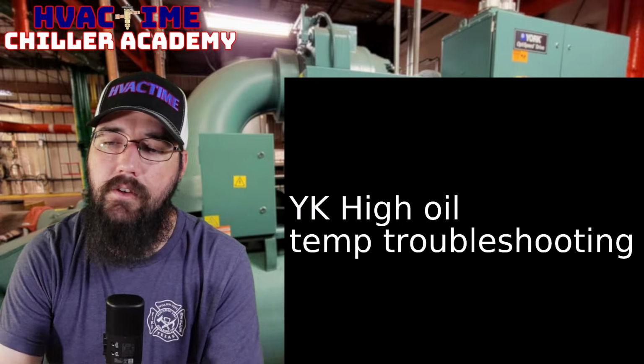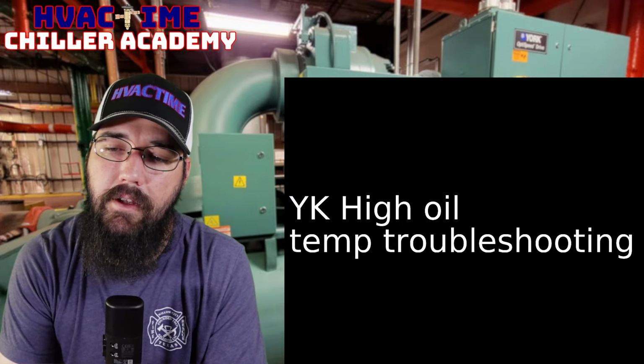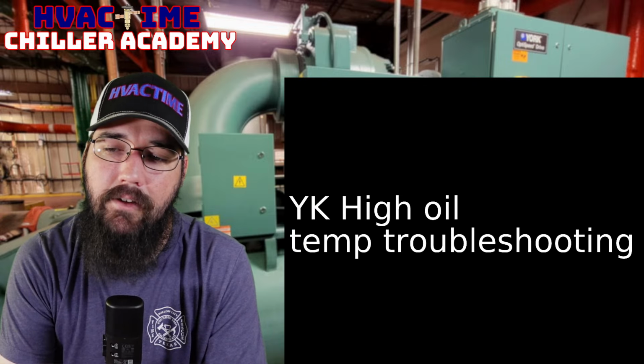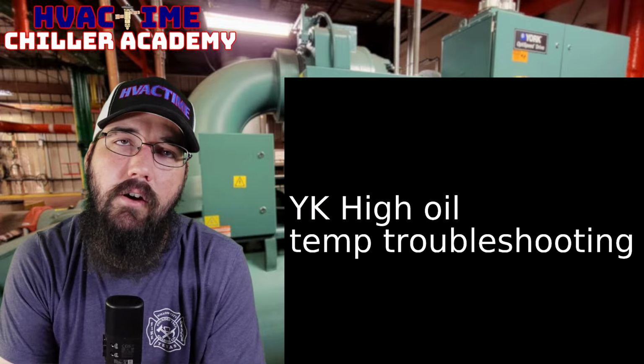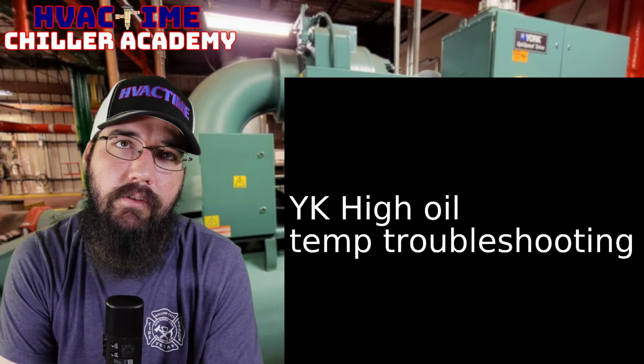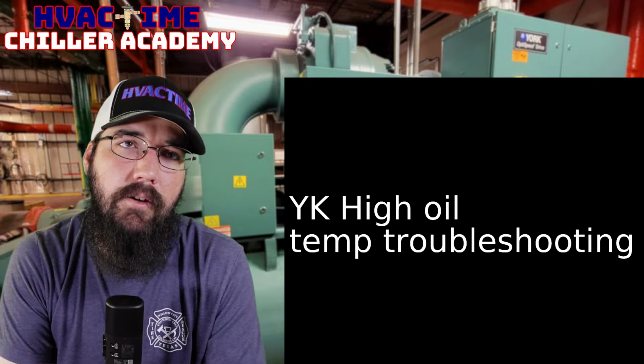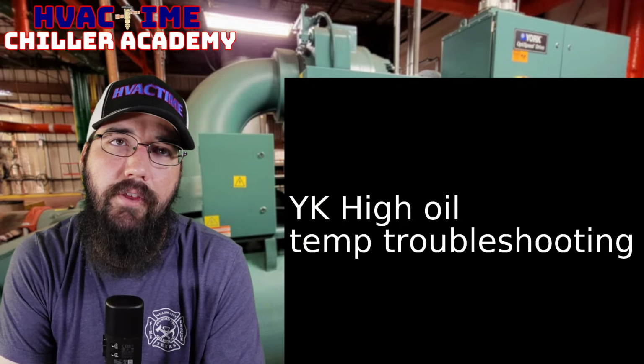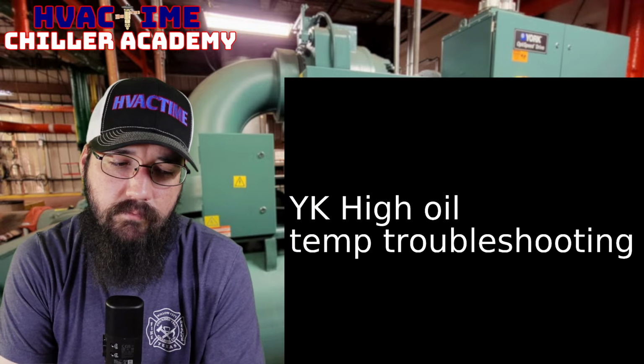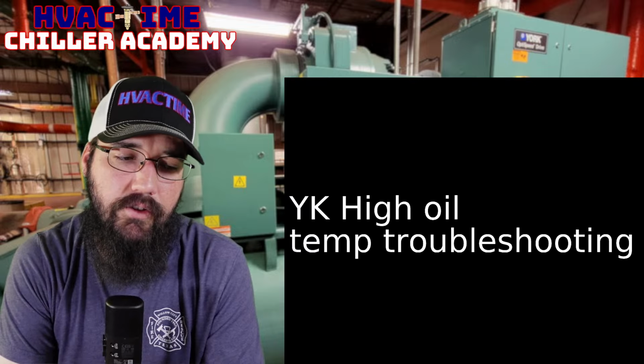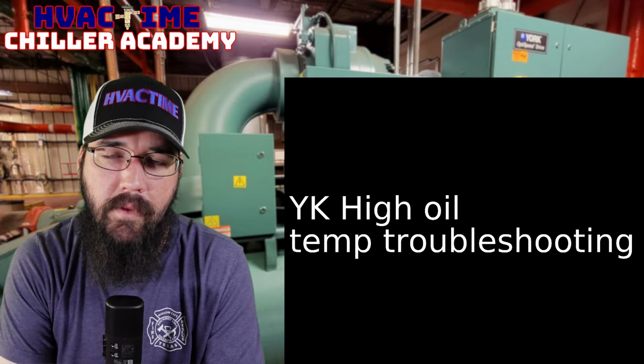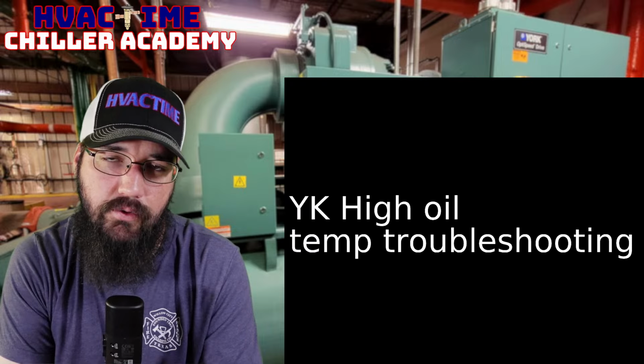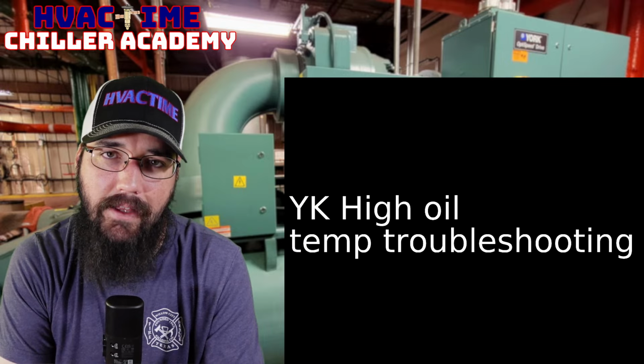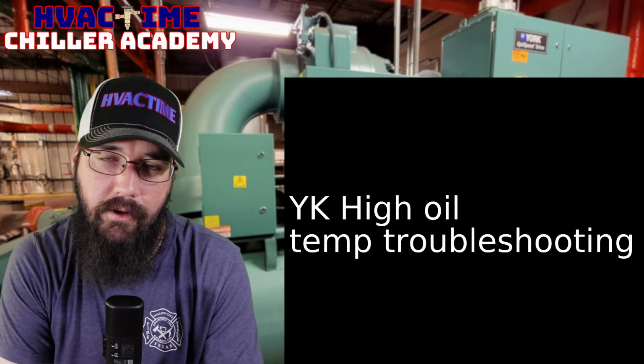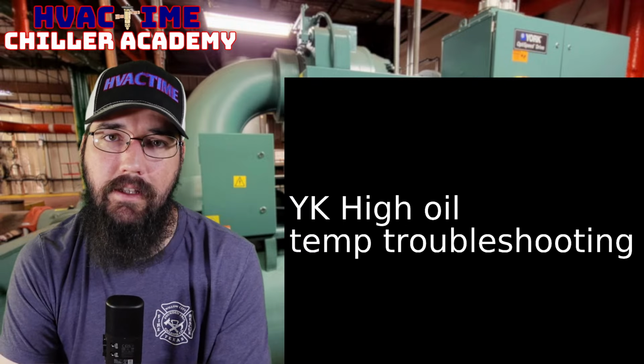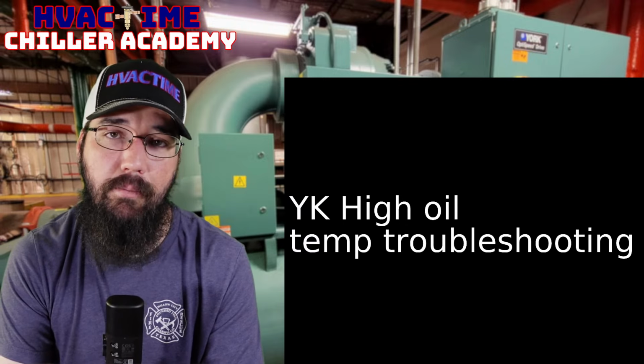So I don't think so. Then the next part of that question would be: does the condenser water increasing in temperature have an impact on the oil temperature? Well, it's going to increase our head pressure. It's going to increase our condenser pressure, obviously. So the only reason I would think that would affect our oil temperature is if it's causing us issues maintaining subcooling. Because if we start having subcooling and liquid level issues in the condenser, that's going to impact the oil cooler metering device. Because keep in mind, YKs do need subcooling, especially when loaded, to operate properly and efficiently.